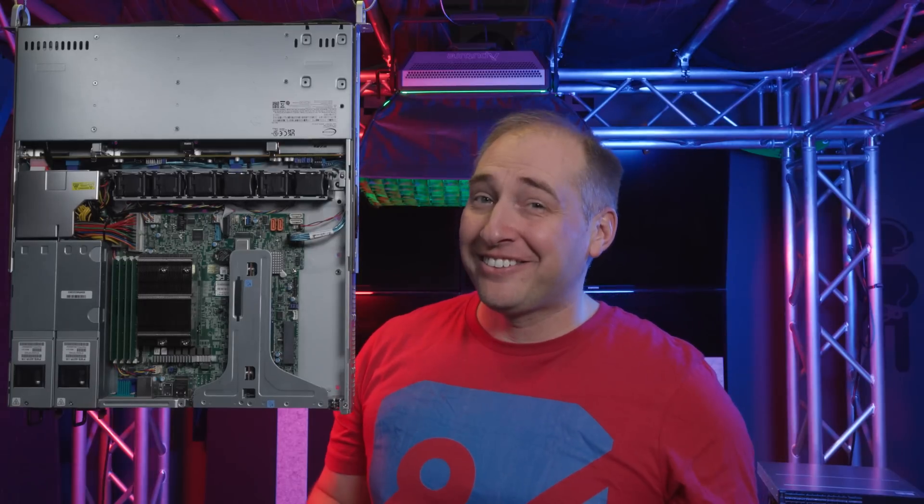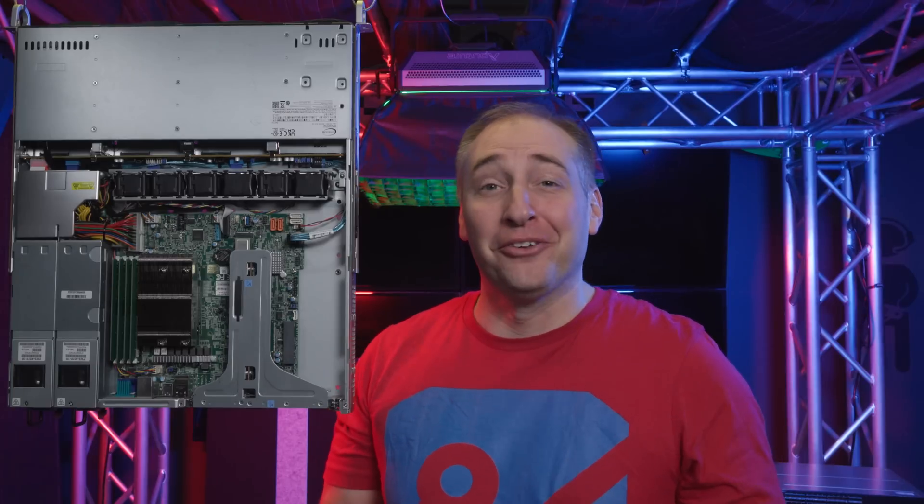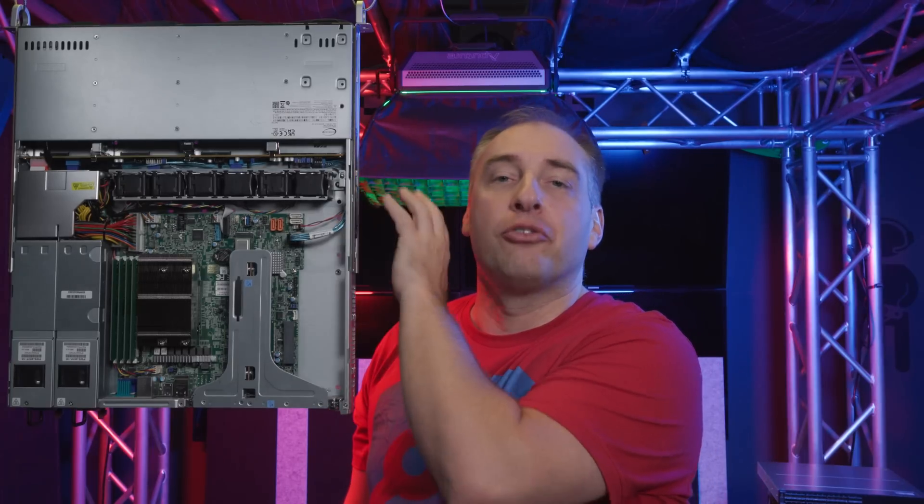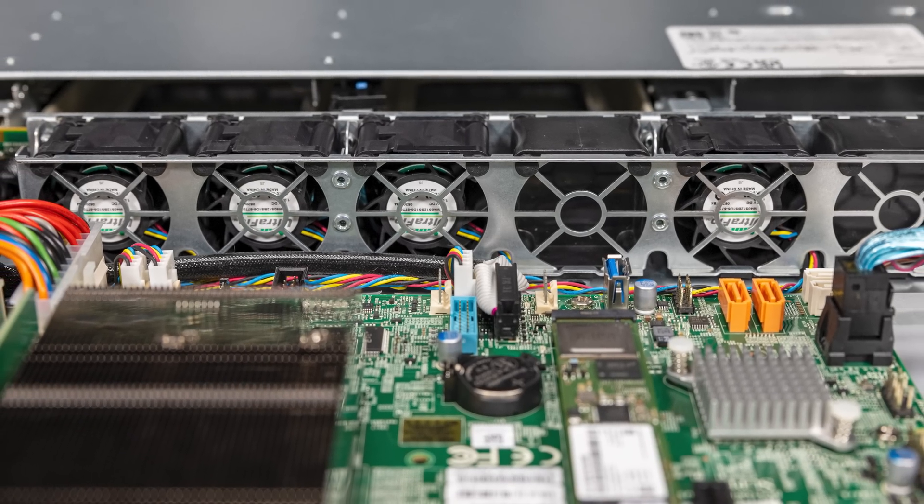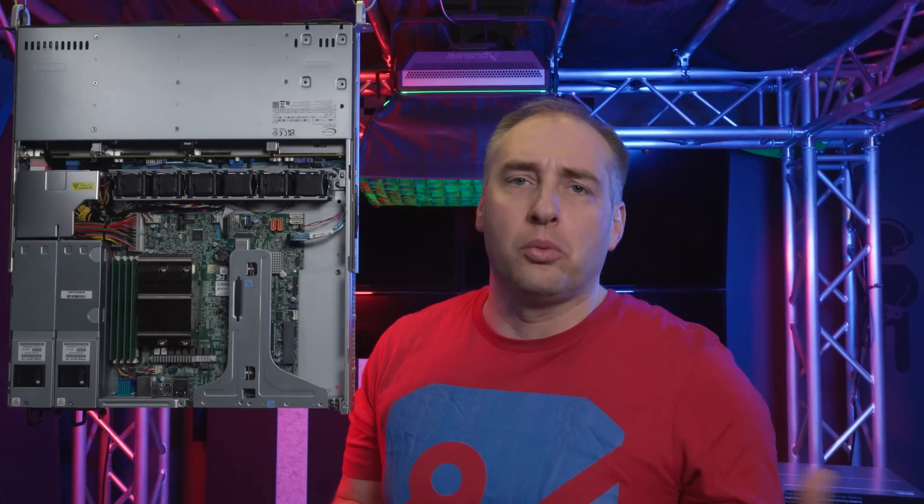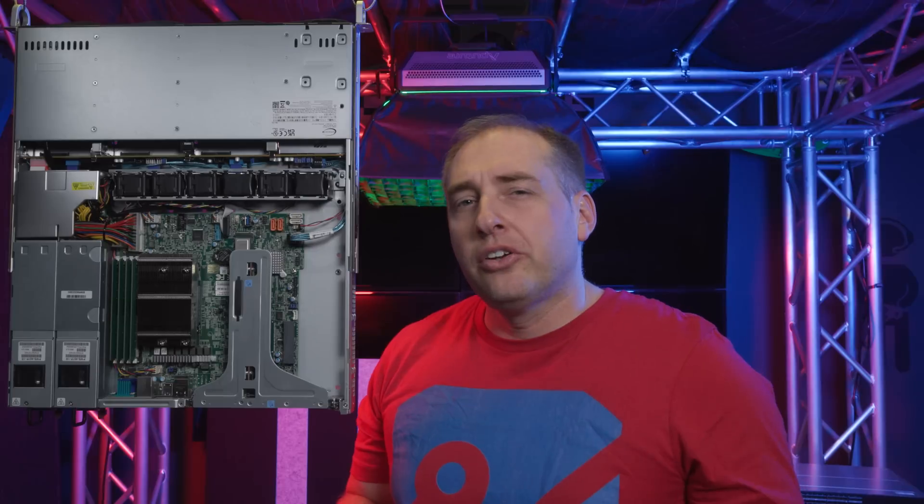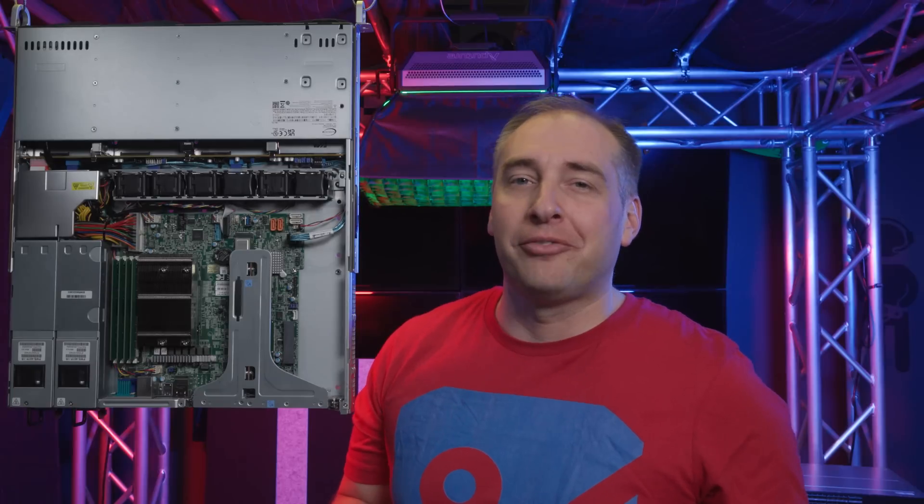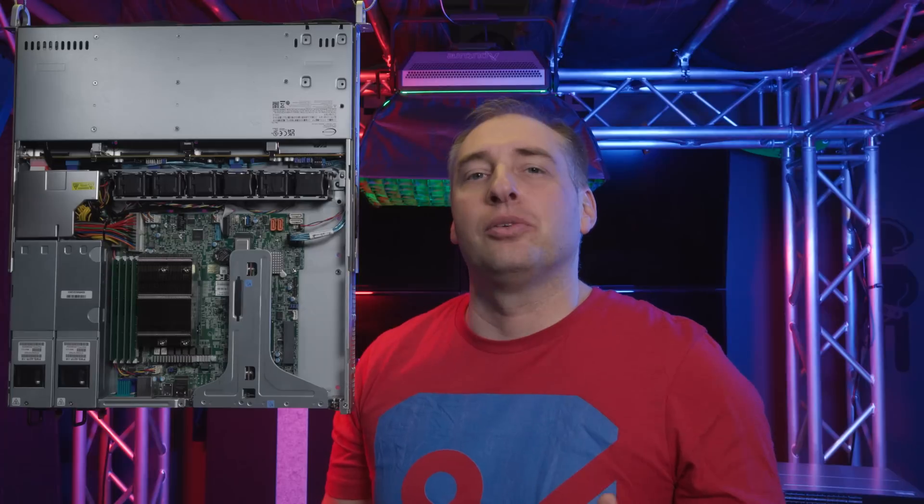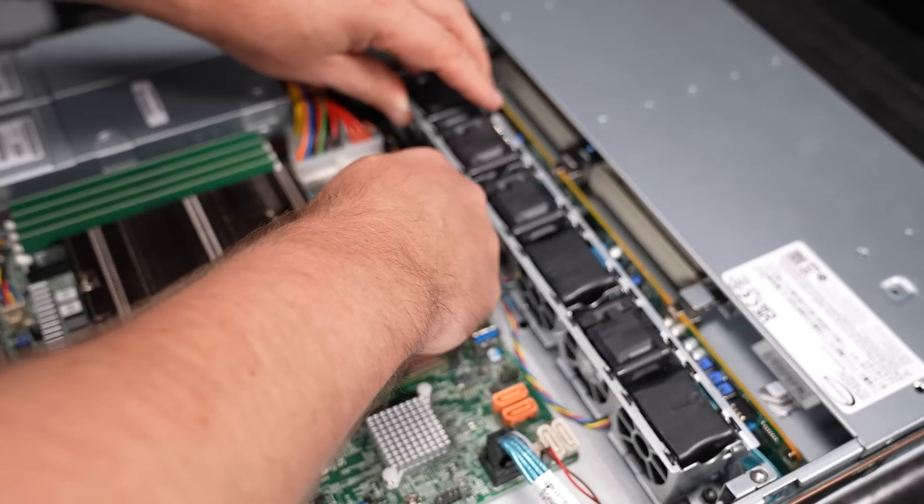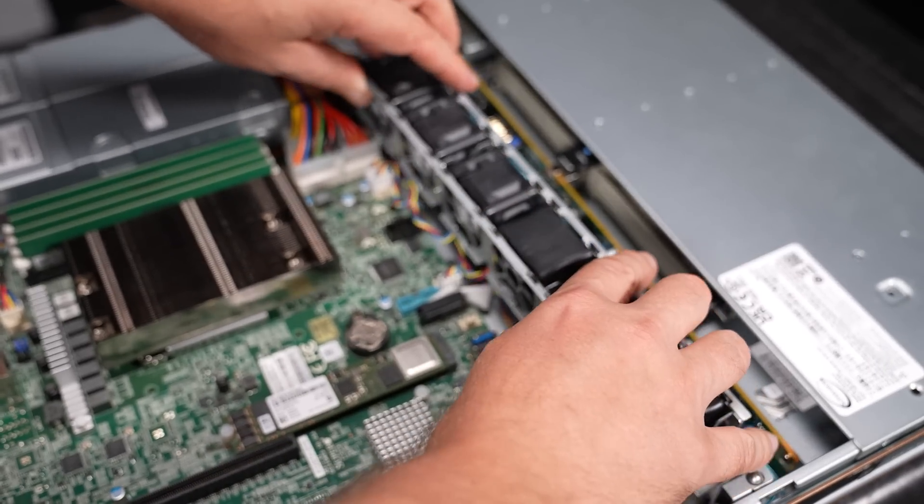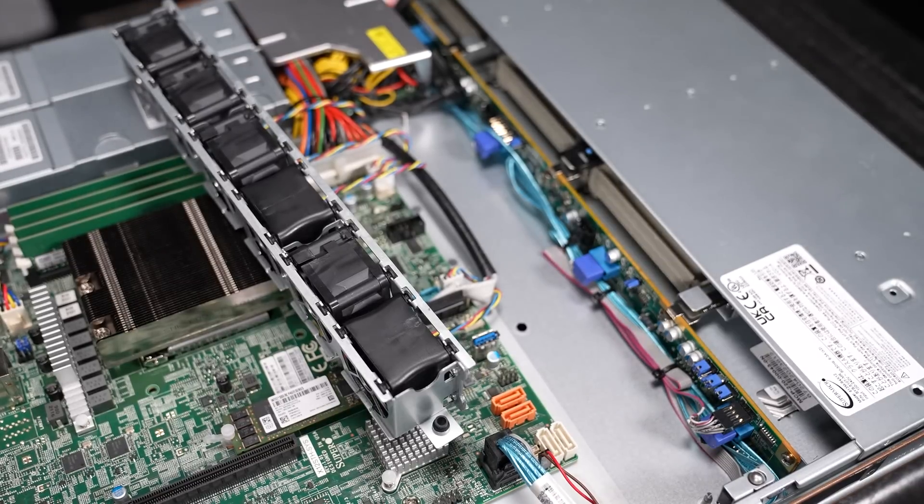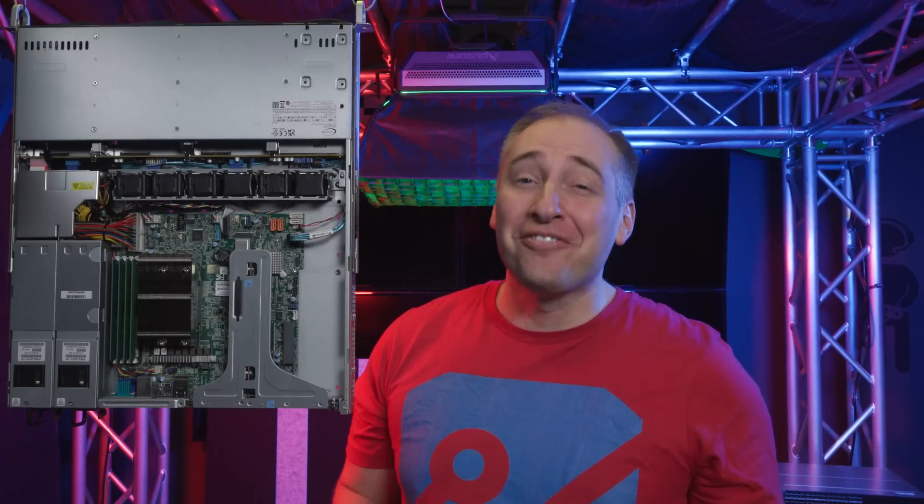All right, so let's get inside the system because this is not the biggest system. But on the other hand, it is super cool. And I'm getting really excited because we're getting close to the motherboard. Now, the first thing that you're going to notice behind the backplane for the storage up here is you're actually going to notice that we do have a fan array. Now in our particular system, only four of the six fan slots are actually populated. You could add another fan if you totally wanted to. We have blanks in here instead. And that's just how Supermicro actually sent this to us. And one thing to note is just 1U fans are typically, especially in this segment, very hard to, you very rarely find true hot swap fans like you find on a lot of the 2U servers. Instead, usually there are cables just due to the actual depth of the chassis in a 1U is just not tall enough to support normal hot swap fans like we would normally see them. And so this does not have that, but it does have a kind of cool feature that you can actually pull out this entire fan partition all in one go. It's on little rubber grommets for vibration dampening, but you just pull it out and you can start servicing it. So while this is not hot swap fans like you normally see in kind of higher end servers, it is still a pretty decent solution, especially in this segment.